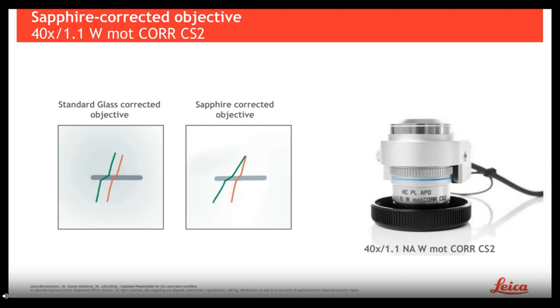We use a specific sapphire-corrected objective for a very important reason. The sapphire has different imaging properties compared to glass. If we used a standard glass-corrected objective, the green and red wavelengths would not focus at the same focal position because of the chromatic aberration of the sapphire, meaning the picture would appear blurry and we wouldn't be able to target very precisely. With the sapphire-corrected objective, this chromatic aberration of the sapphire is corrected so that the different wavelengths focus again at the same z-height inside the sample.